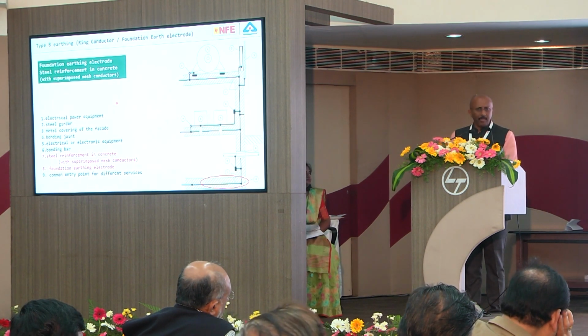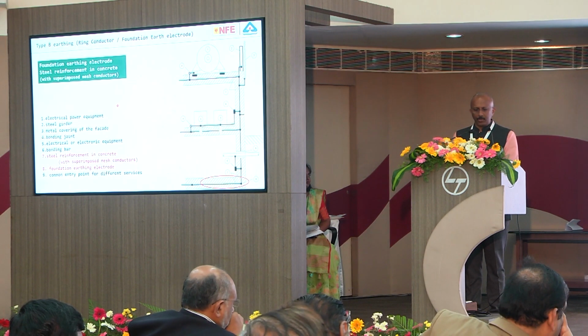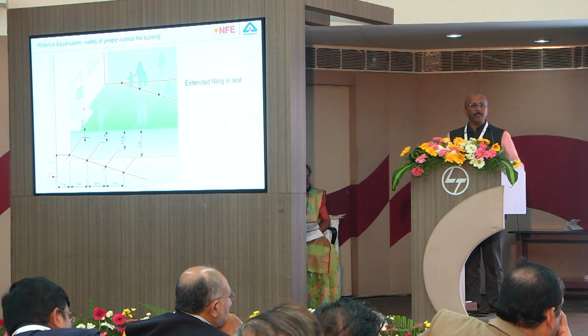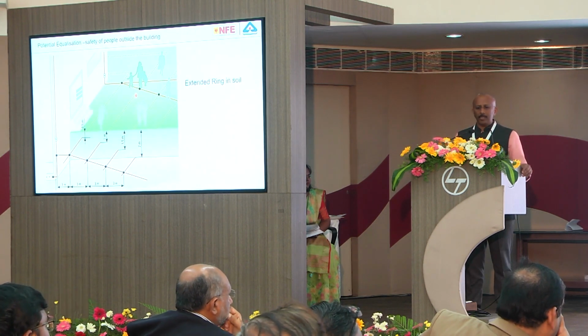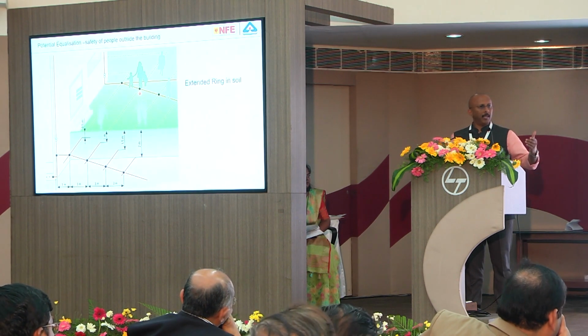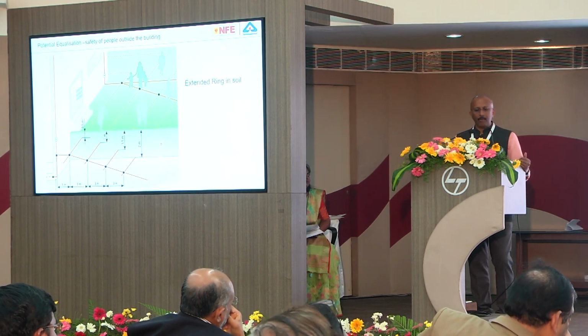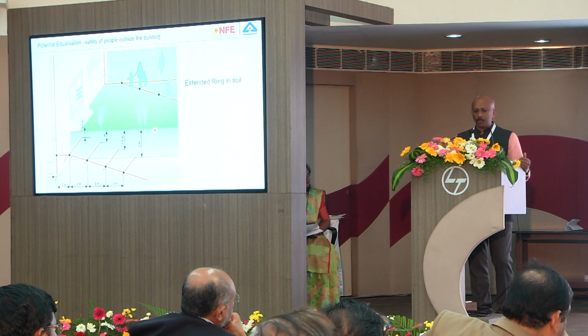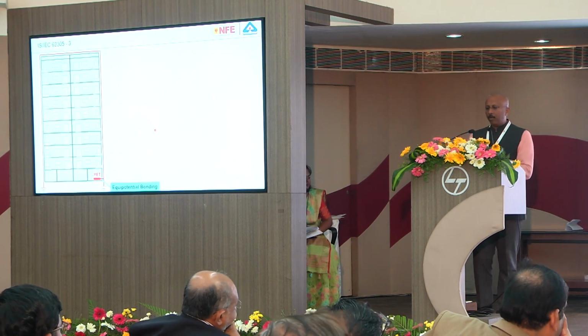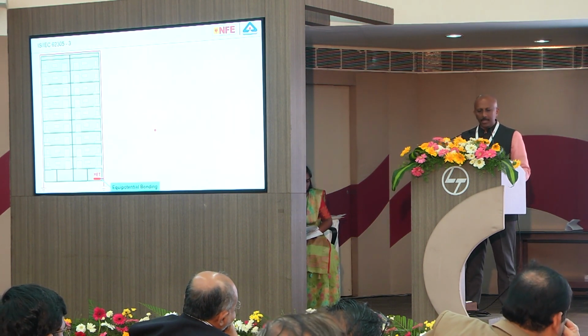So just an example, you can find this picture in NBC and IEC 62305. One of the techniques which is included or is going to come in the new standards, I think this is also included in the NBC, is protection of people outside the building, because during a lightning strike, if people are outside the building, due to step voltage, people can be injured, and if you make this kind of additional ring, extended ring in soil, we can protect people from step voltages. Now we go to another interesting subject of lightning protection, which is, you see here, there is a building.